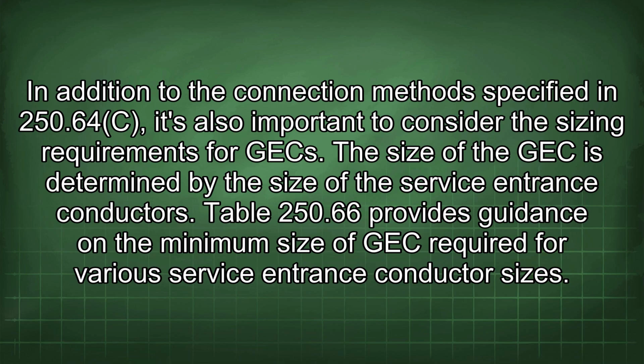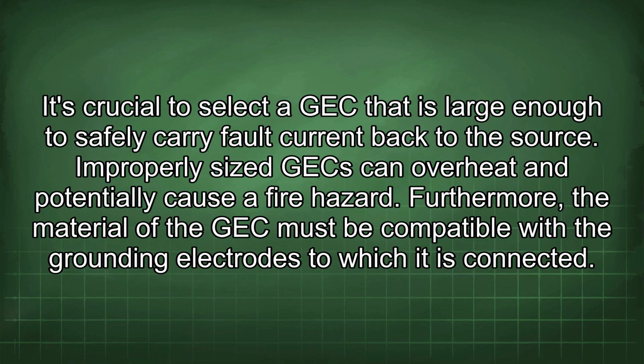In addition to the connection methods specified in 250.64(C), it's also important to consider the sizing requirements for GEC. The size of the GEC is determined by the size of the service entrance conductors. Table 250.66 provides guidance on the minimum size of GEC required for various service entrance conductor sizes. It's crucial to select a GEC that is large enough to safely carry fault current back to the source.